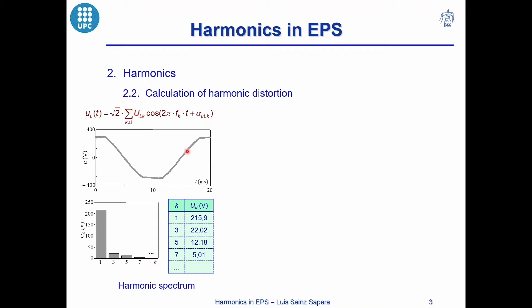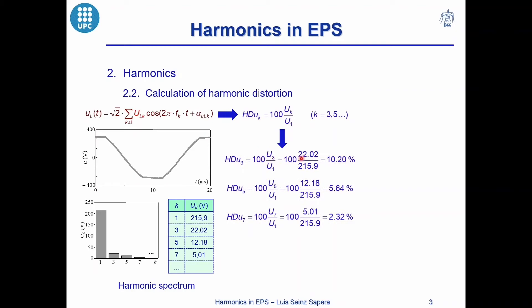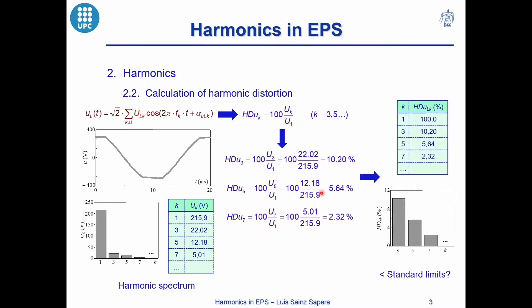To illustrate this, I will analyze the following example. We have a distorted voltage with the root mean square values of the fundamental and the harmonics shown in a table, and I would like to determine the degree of distortion of the voltage. First I will calculate the individual harmonic distortion for each harmonic, dividing the root mean square value of each harmonic by the root mean square value of the fundamental waveform. These results can be shown in a table or in a bar plot and compared with the limits of the standards.